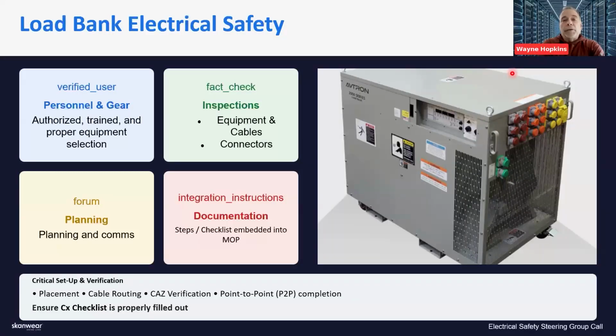And when we're load banking, understanding we're load banking through permanent systems, so cable conductors like this load bank, let's just call them load bank cables, should be, if they are UV deteriorated, phase coloring deteriorated, at least labeled on each end: A phase, B phase, proper gauge size, proper length of that cable. All of that should be there, and maybe last inspection date on that label, and again at both ends, those are the things you want to see.